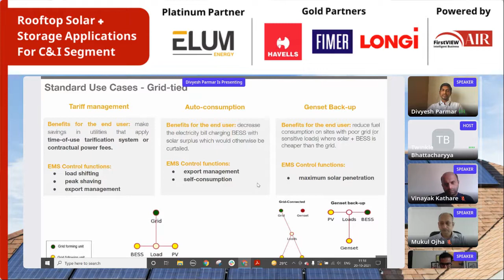Here, the batteries are charged with surplus solar power which would otherwise be curtailed, and this power is reused when the tariff of the region is high. We call this auto consumption, and here the EMS control functions are export management and self consumption. The third application is very straightforward: genset backup, where the benefit is fuel cost saving for the gensets.